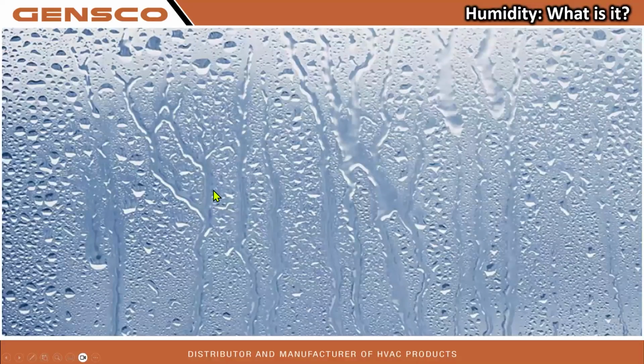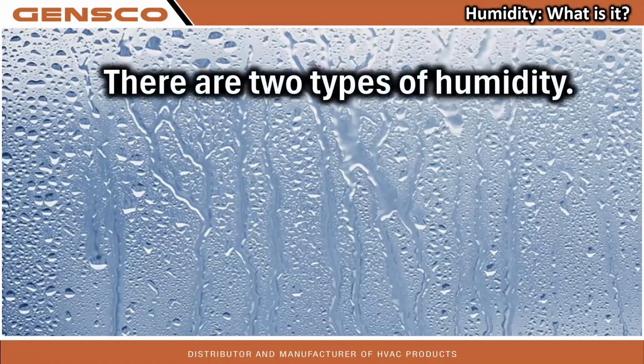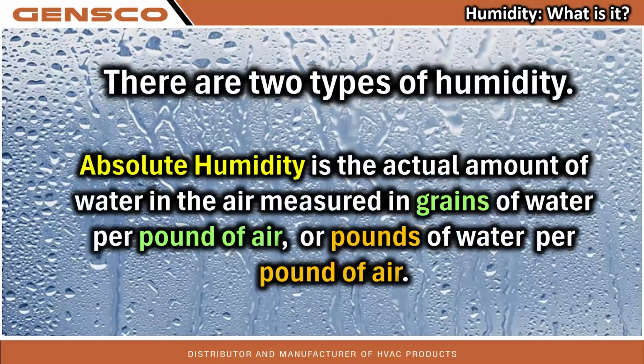Then there's another type of humidity. This one comes a lot into play in engineering because it actually involves water and how much we need to remove. The other type of humidity is called absolute humidity. This is the actual amount of water in the air, measured in either grains of water per pound or pounds of water per pound of air. When we talk about dehumidification, we're talking about physical amounts of water we're going to remove from the air.